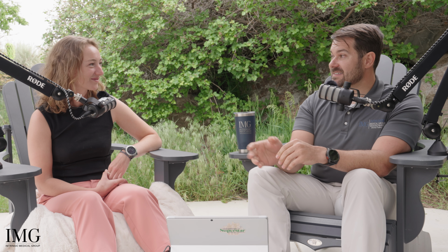I have seen with like cobalt chrome where you couldn't get it machined into the appropriate size, and so we sent it to the lab to have them try to cut it, and then them using plasma cutters and other things to try to cut this, and then changing surface characteristics and or adding residuals. And then we need to sterilize it. There's a lot of things that can get complicated really quick or go wrong with this if you just blindly send and say, cut them up and figure it out.